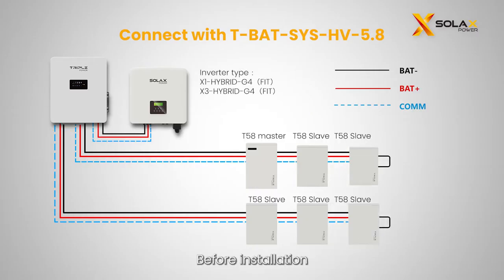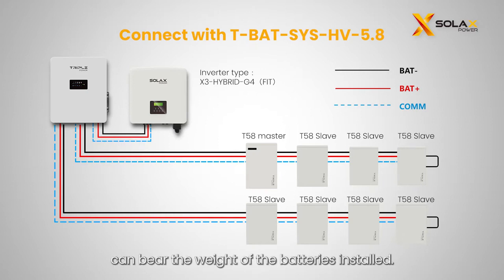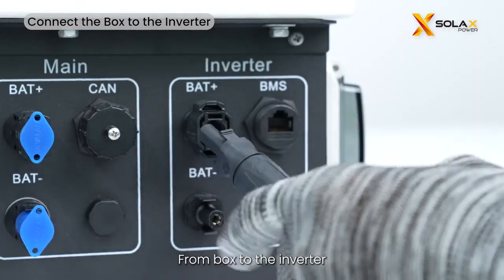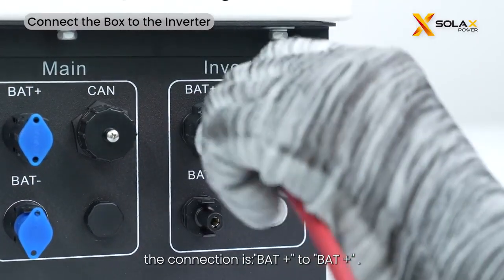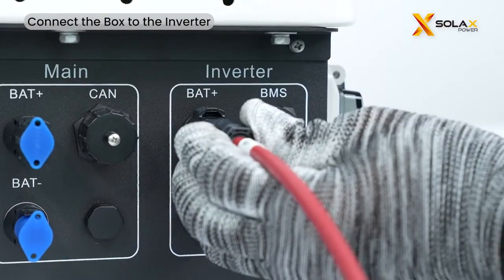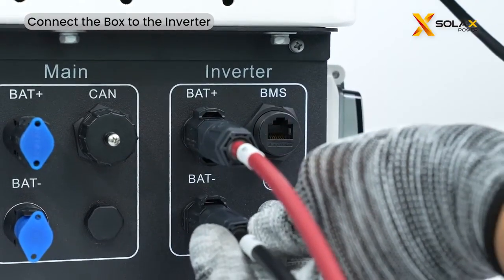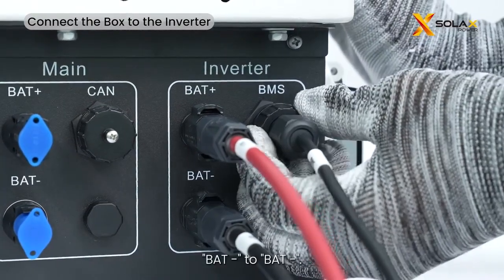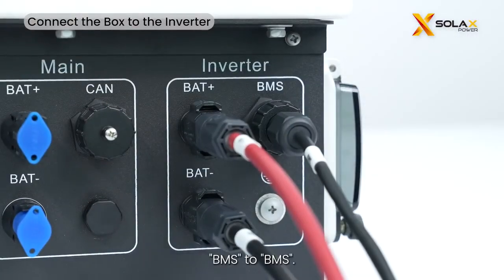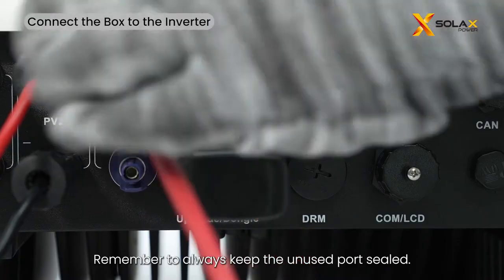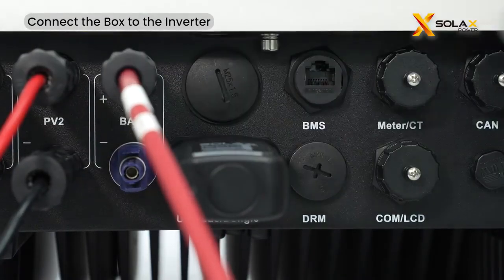Before installation, please make sure that the wall can bear the weight of the batteries installed. If not, please use floor installation. From box to the inverter, the connection is BAT positive to BAT positive. BAT negative to BAT negative. BMS to BMS. Remember to always keep the unused port sealed.